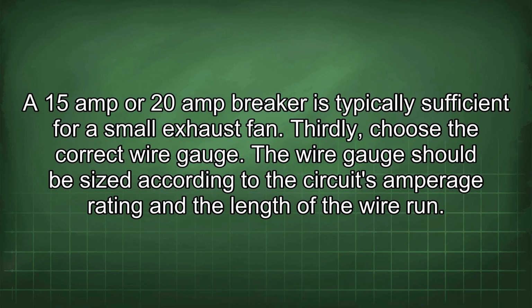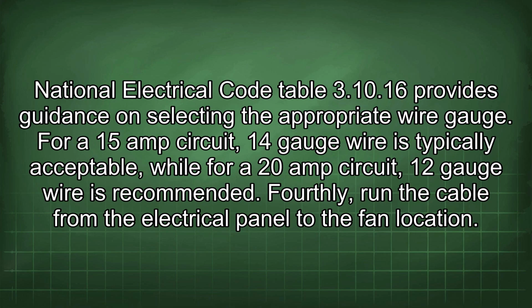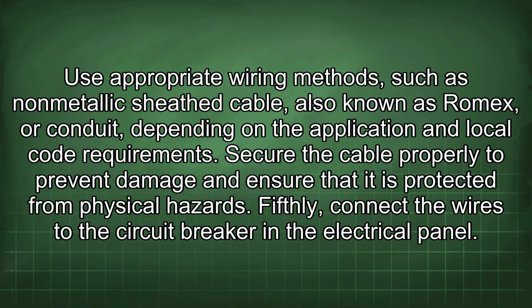Thirdly, choose the correct wire gauge. The wire gauge should be sized according to the circuit's amperage rating and the length of the wire run. National Electrical Code Table 3.10.16 provides guidance on selecting the appropriate wire gauge. For a 15 amp circuit, 14 gauge wire is typically acceptable, while for a 20 amp circuit, 12 gauge wire is recommended. Fourthly, run the cable from the electrical panel to the fan location. Use appropriate wiring methods such as non-metallic sheath cable, also known as Romex, or conduit depending on the application and local code requirements. Secure the cable properly to prevent damage and ensure that it is protected from physical hazards.